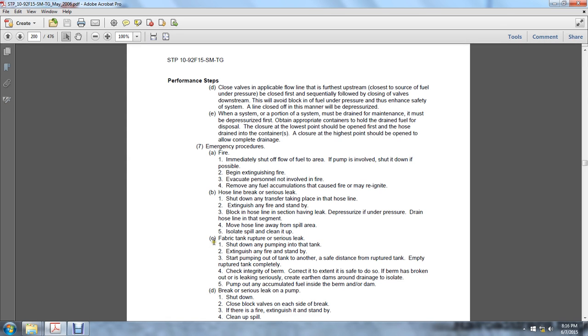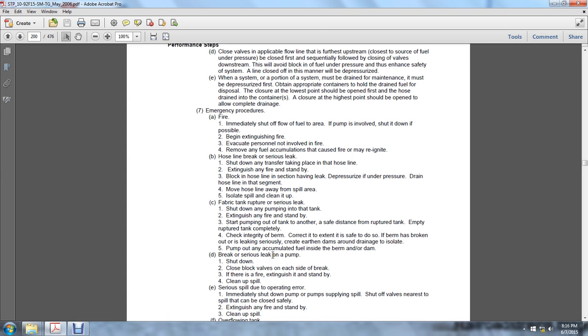Fabric tank rupture or serious leak. Shut down any pumping into the tank. Extinguish any fire and stand by. Start pumping out of the tank at a safe distance from the ruptured tank. Empty the ruptured tank completely. Check the integrity of the berm and correct it to the extent that it is safe to do so. If the berm has broken out or is leaking seriously, create earthen dams around the drainage to isolate and pump out any accumulated fuel inside the berm or the dam.